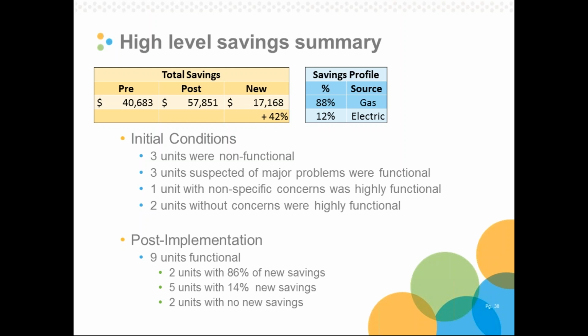All of our savings, or like 86% of our savings, came from fixing 2 units. 2 of these initial units that were non-functional were relatively large, and by getting them basically functional, we recovered most of our savings. That means that on the 5 units where we implemented the other savings, we only recovered 14% of our net savings, so a few $1,000s. In other words, getting units from not working to working was very cost effective. Fixing a bunch of minor issues on basically functional units was not cost effective. And then we did not find any savings on our 2 units that we hoped were working great.